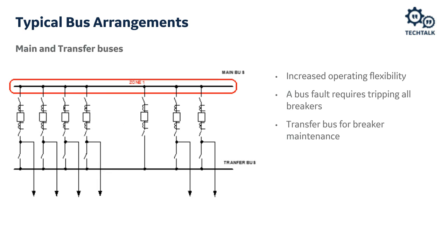The main and transfer bus scheme has a transfer bus where normally all loads and sources are connected from the main bus. If a fault occurs on the main bus or a bus outage is needed, loads and sources can be quickly restored by transferring to the transfer bus. Also, if a breaker needs to go out for maintenance, that load can be transferred to the transfer bus using the bus tie as the breaker for that load, offering really good flexibility for outages and maintenance.